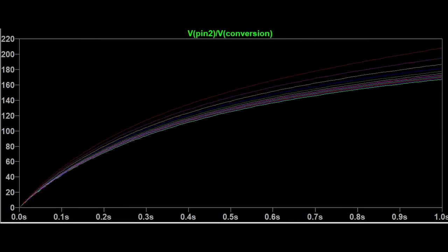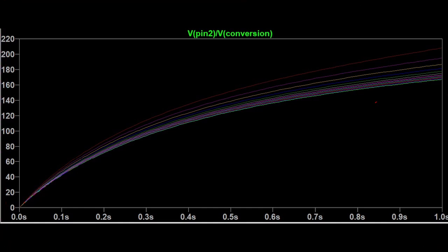Simulation results. The simulation results clearly reveal the same issues we have already observed in practice. Limited adjustment options. The maximum current regulation only allows a restricted adjustment between 160 ampere and 200 ampere, making fine-tuning difficult. Nonlinear welding current regulation. The output characteristic of the welding current is not proportional to the pedal position, leading to uneven control. In the next section, I will present my solution that solves these problems and enables more precise, linear control.